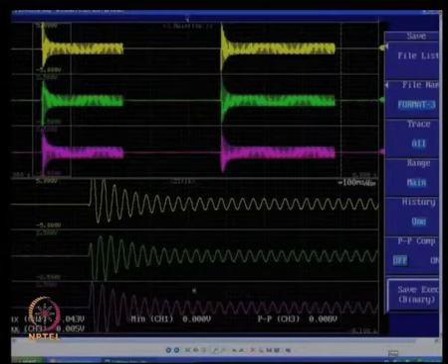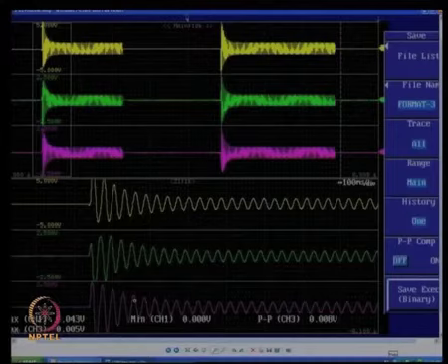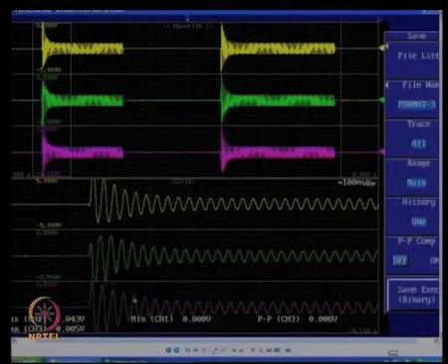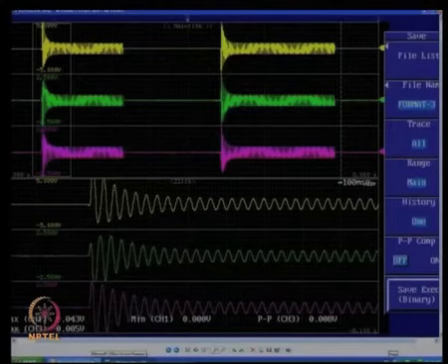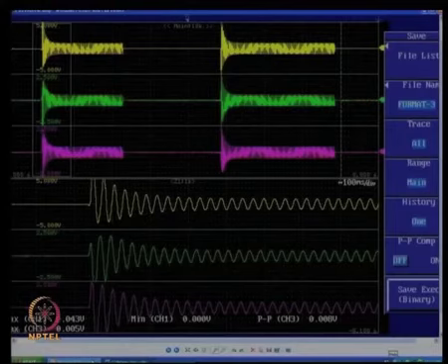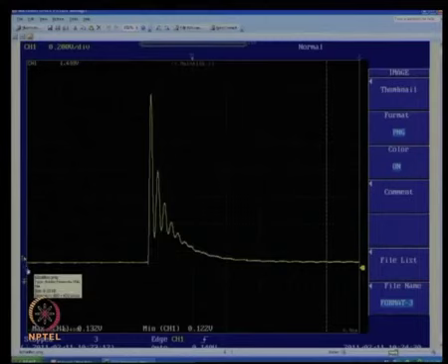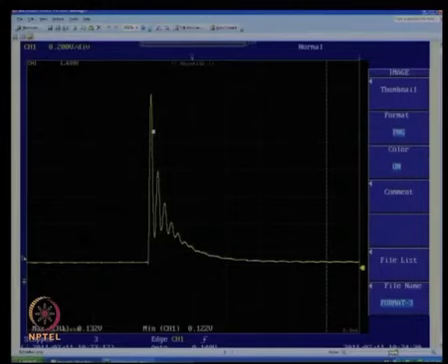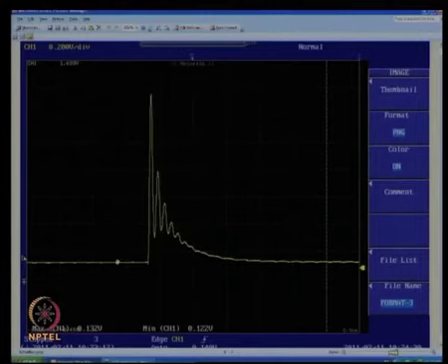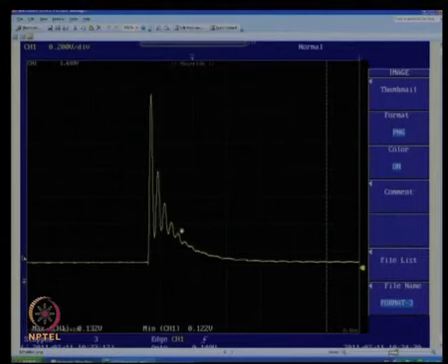There is another figure I would like you to see, that of the field current under these conditions. When I gave you a short circuit, your field current is also affected, and what you notice here, this is something I did not show in the live experimental demonstration, but we captured this waveform by performing the experiment again. This is the field current, which you see initially there is some current value in the field winding. As soon as you apply the short circuit there is an oscillatory response. Normally the field current is a DC current, but you see an oscillatory response which dies out with time as well as an exponential decay.